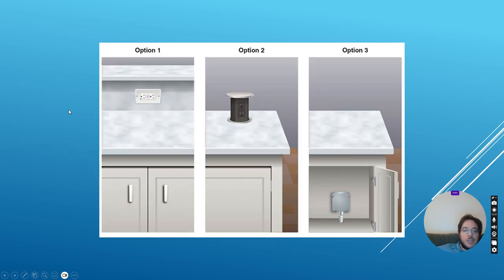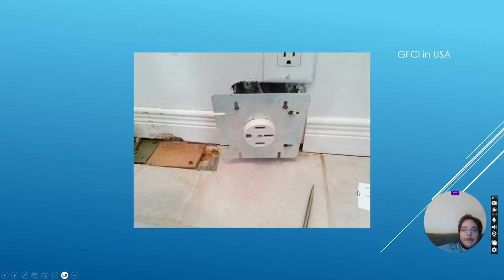And you got 3 options. So if your island has what's called an overhang, then you can put the receptacle inside the millwork, or what's more likely and much more common and being mandated is what's called the pop-up receptacle, or in some cases they make an exception, and you don't have to put the receptacle, but you do have to rough in for it so that it could be added later.